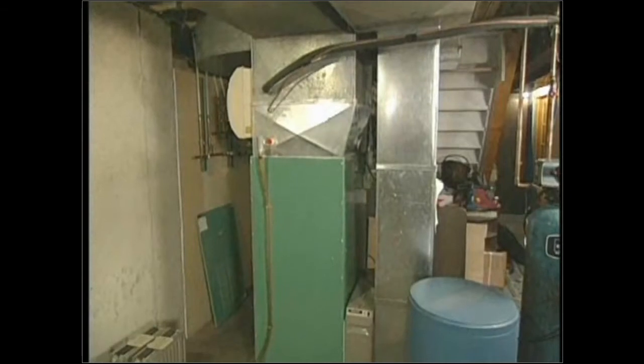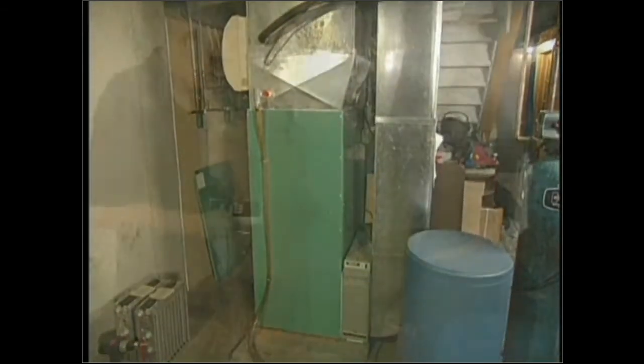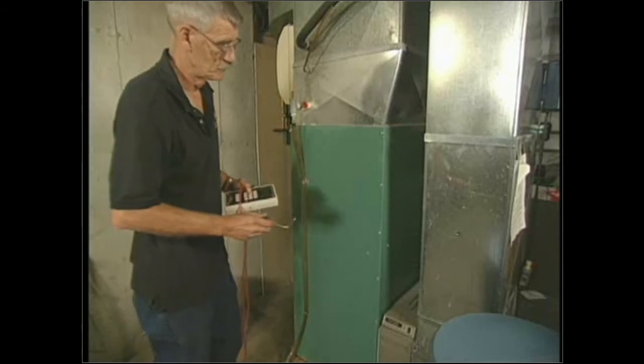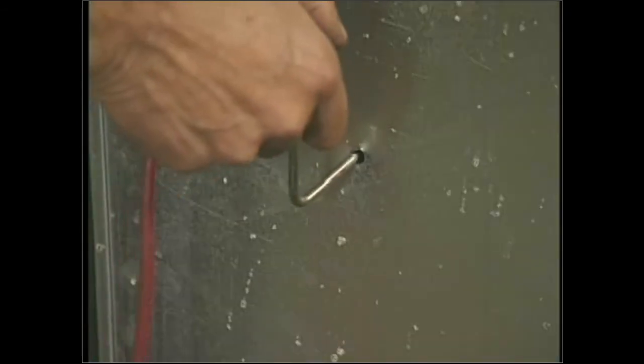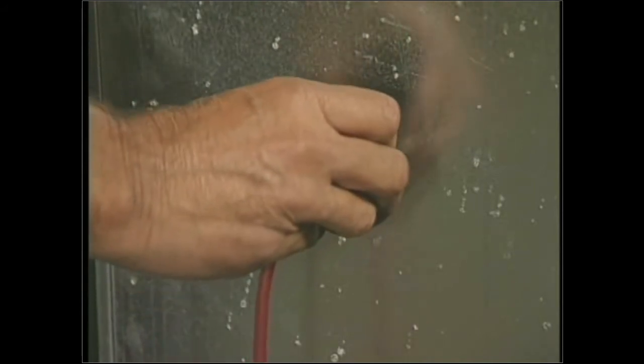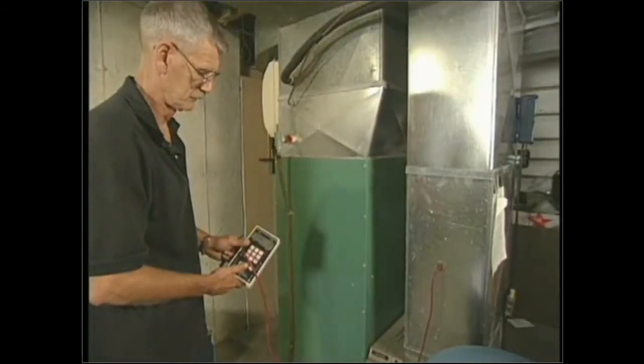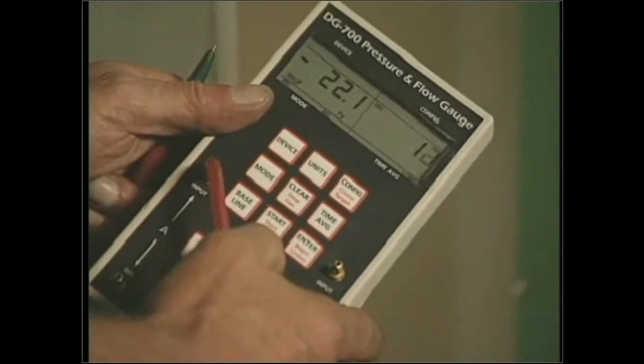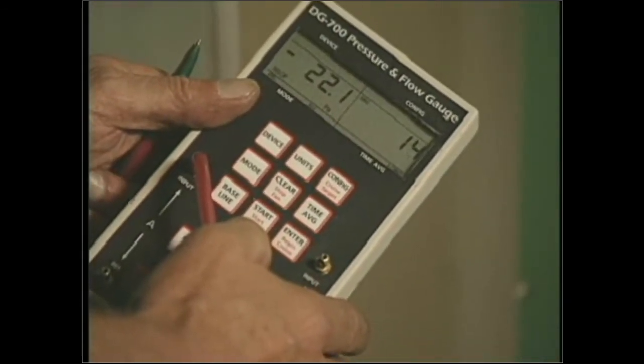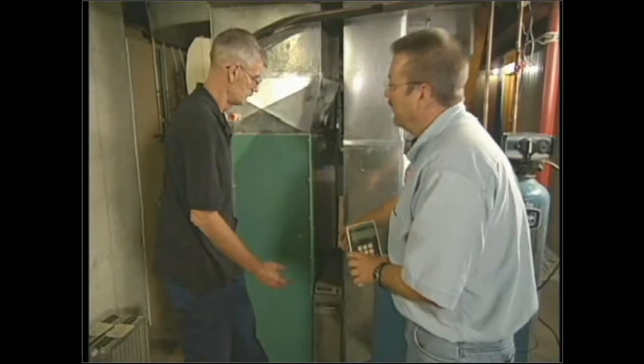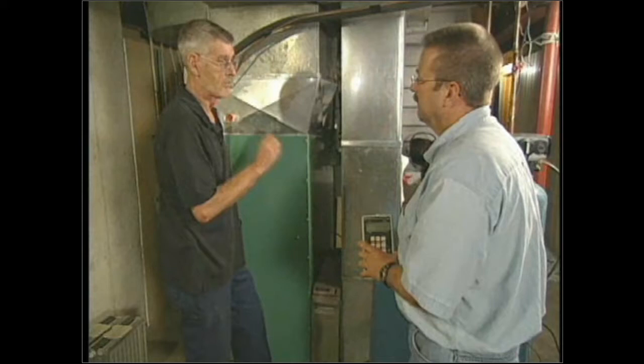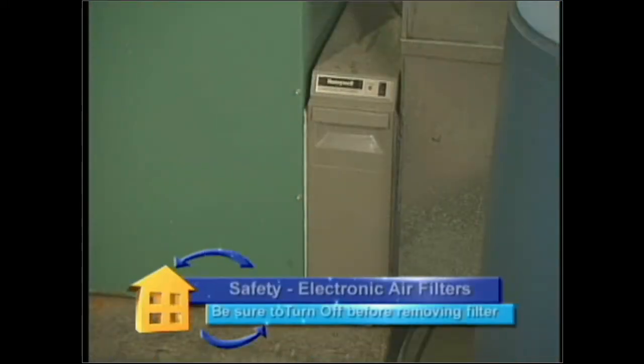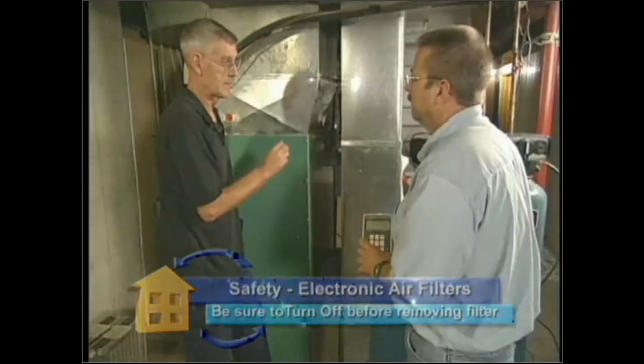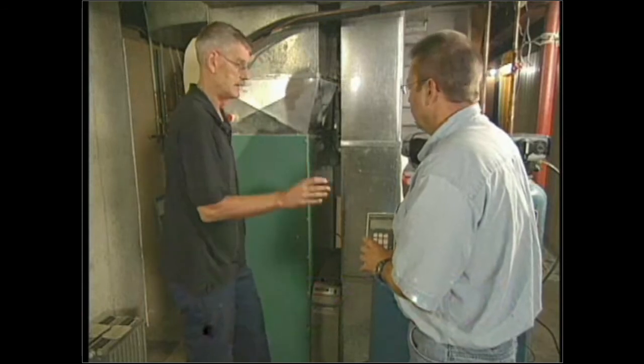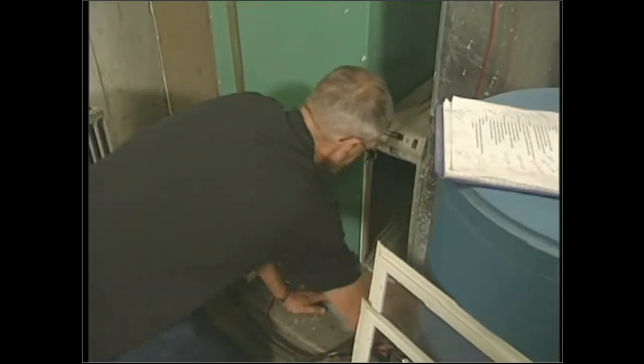We have to put a hole in our return drop midway point, which we've already got selected because we've used a temperature rise taken there. And we'll take the static pressure probe, stick it in the direction of flow, connect it to our manometer, and do a TESP test, which means we take a reading of what the static pressure in here is, so we have it in the calculation. And that's leaving the homeowner's filter in place. Yes, always done with a clean homeowner's filter. That's what we're doing right now: we're measuring the resistance between the filter and what the flow plate would be. Okay, so you take that reading. Yep. Okay. Once we have that test, what we need to do is pull the homeowner's filter out and insert our flow plate.